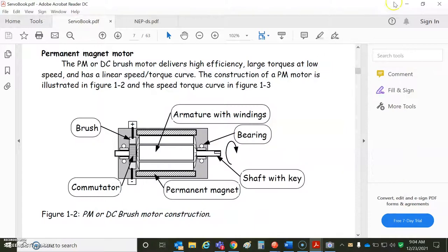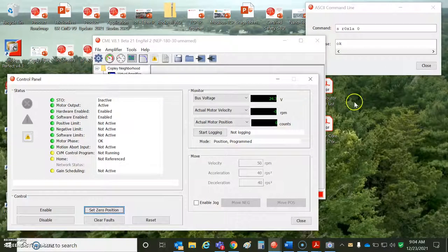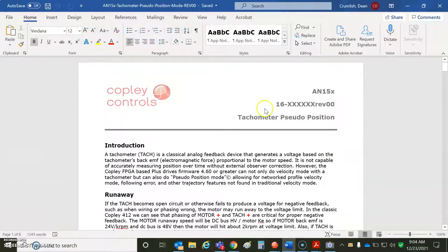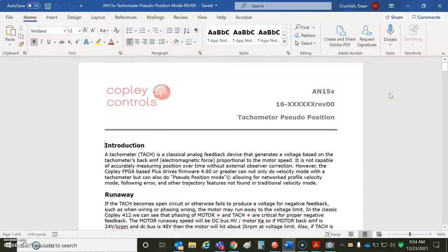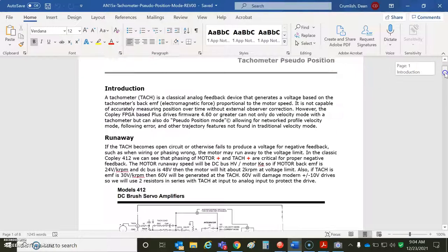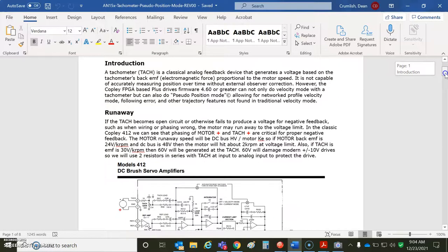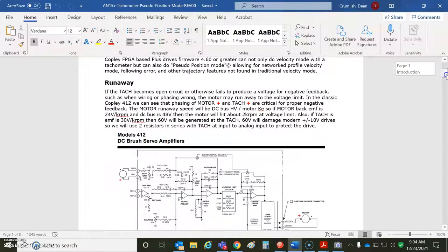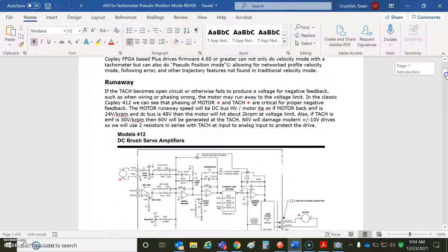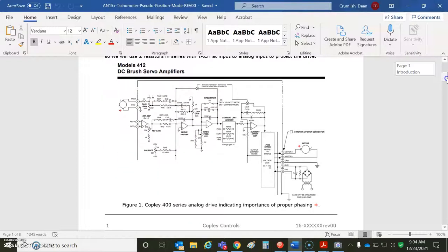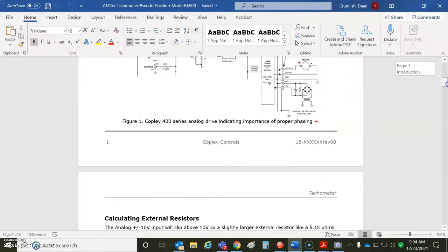So the basic idea is that we're going to do a tachometer in a pseudo position mode. You can't really hold position. It's going to drift as you see based on offset. We can try to compensate for that. But maybe over temperature or time, you'll get a little drift out of it. So pseudo position, it's not real position. But it's good for profile velocity and using network systems. Be careful when you're hooking up the tach. If you hook it up backwards, it runs away. I just swap motor wires. Same rules as the old Copley 412.